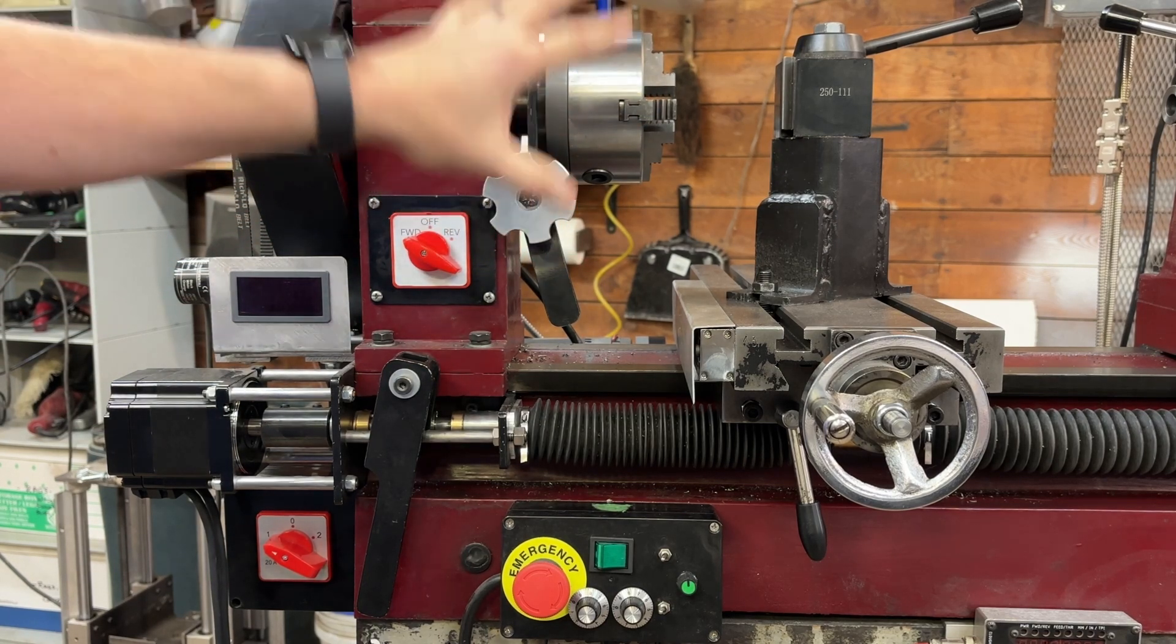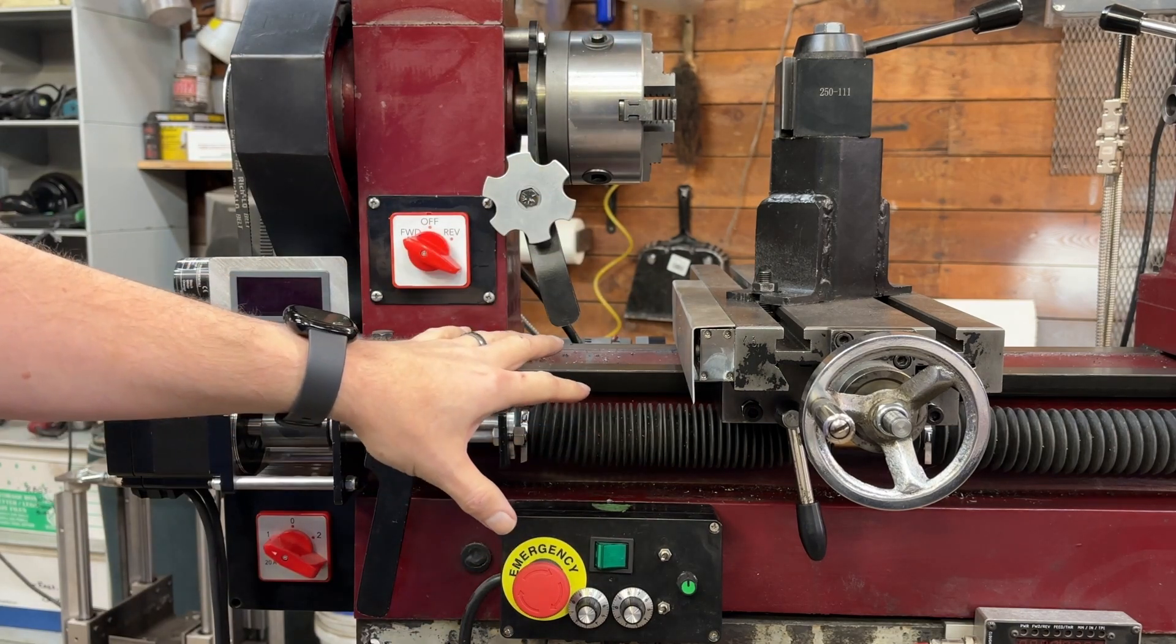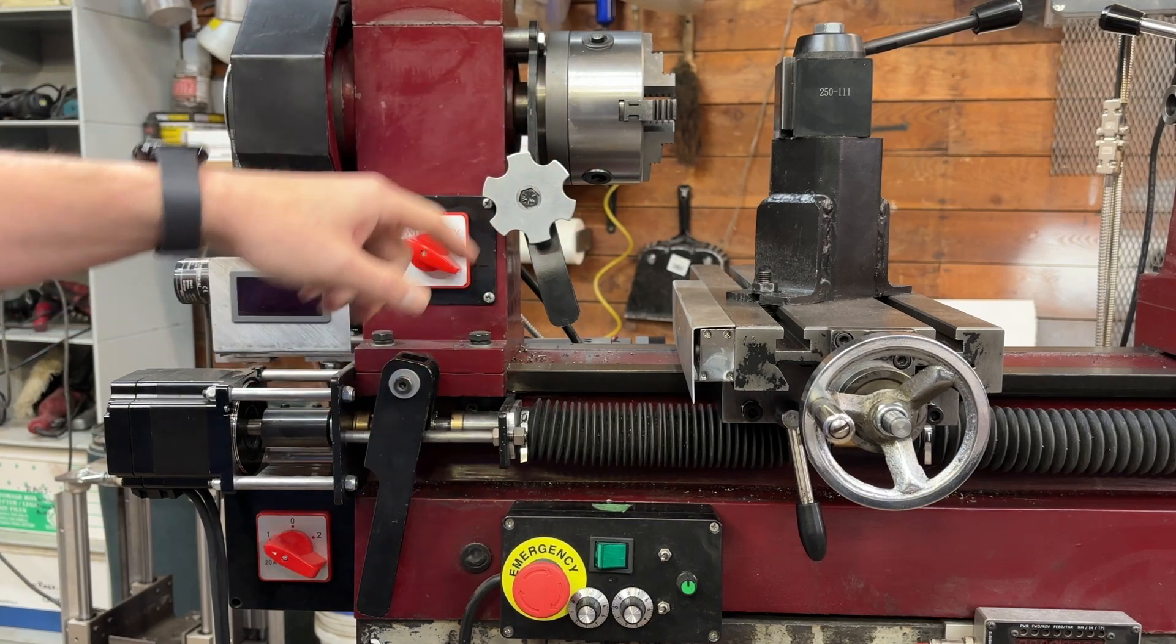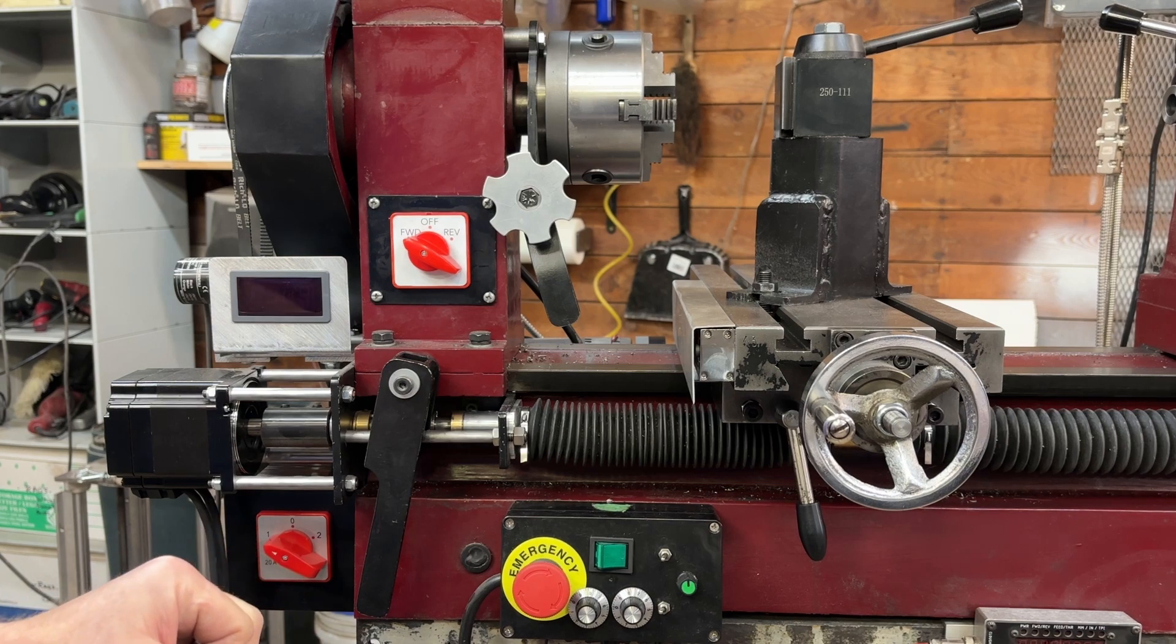That shows the braking system is working. The relay on the back is controlling the connection between the motor and the resistors and seems like no issue, no problem.